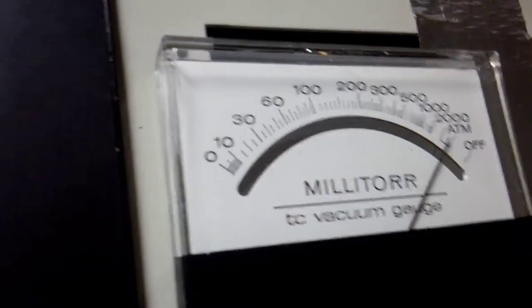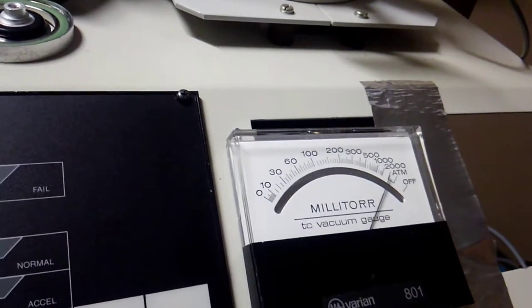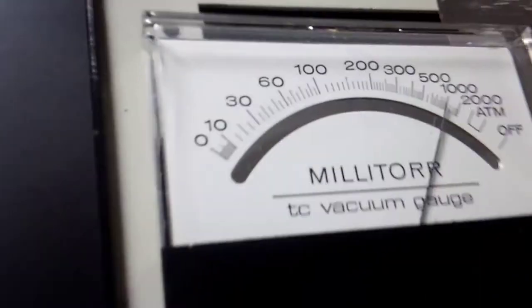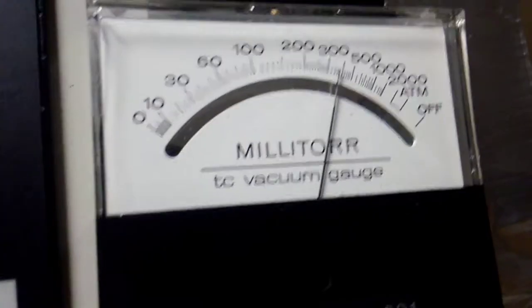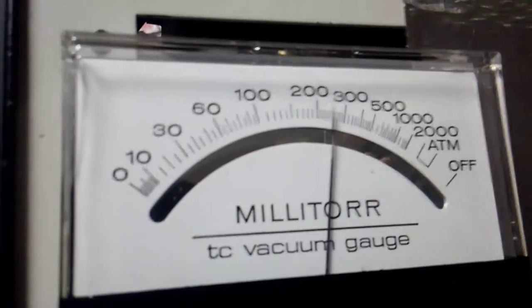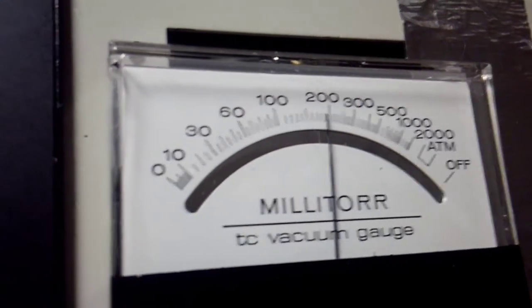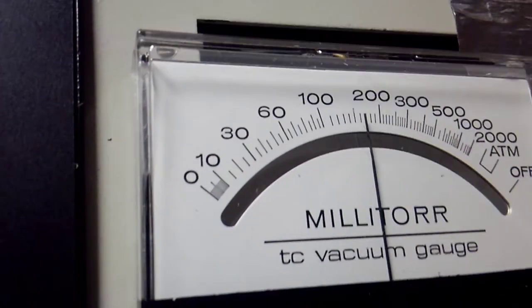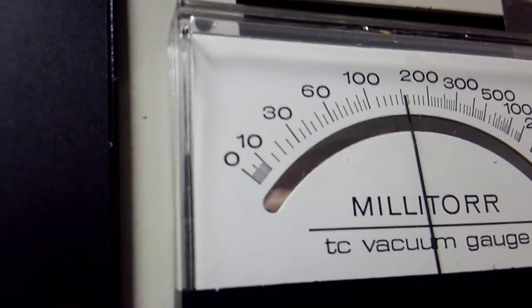When it gets down to about 100 millitorr, then I'm going to activate the turbo pump. Okay, it's getting pretty close to 100 millitorr. The chamber's total volume is probably approximately one liter.